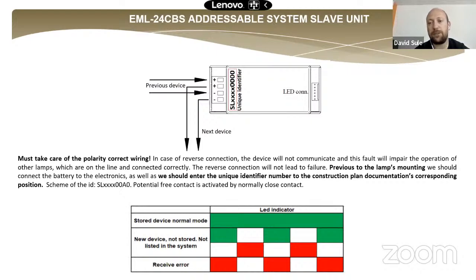If the communication stops between the light and the panel, that will show a blinking red light status. So it's red, red, red, red when the light has received an error. So something happened with the LED driver or with the line driver of the panel. We can read any error information on the LCD screen, the last 2000 events and the last test result.